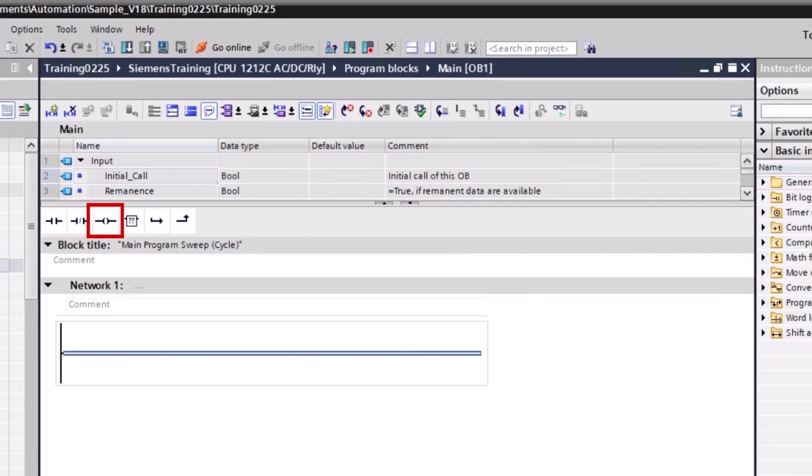You can use the assignment instruction to set the bit of a specified operand. If the result of logic operation, abbreviated RLO, at the input of the coil has signal state 1, the specified operand is set to signal state 1. If the signal state is 0 at the input of the coil, the bit of the specified operand is reset to 0. The instruction does not influence the RLO; the RLO at the input of the coil is sent directly to the output.